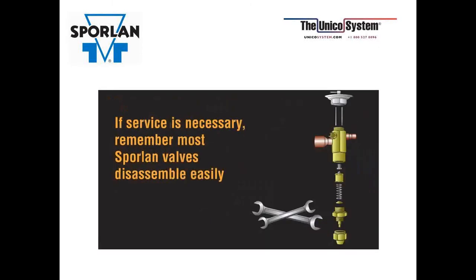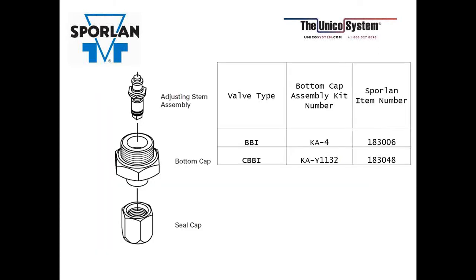But if service is necessary, remember most TEVs can be disassembled easily. And once you take the valve apart, whether you take off the element or you tear the valve apart for cleaning, if it's a non-adjustable valve, what you're going to run into is that you've just changed the factory setting when you put it back together. There's no way to regain that factory setting.